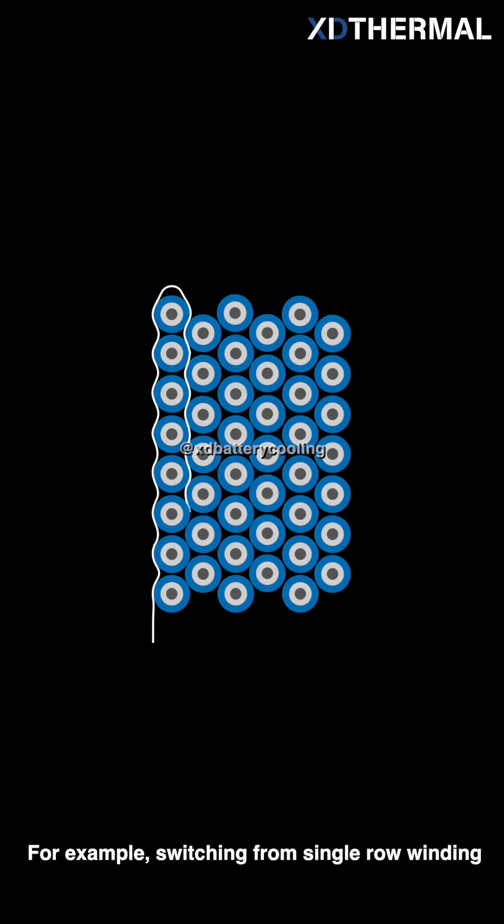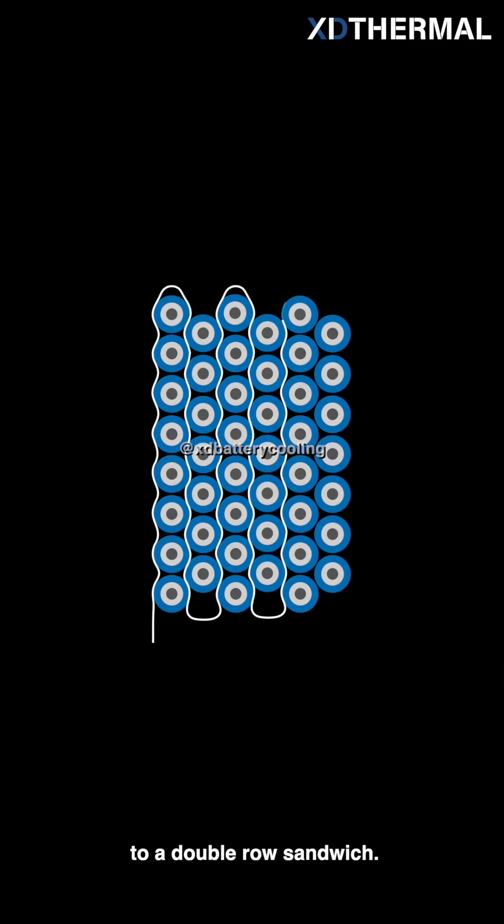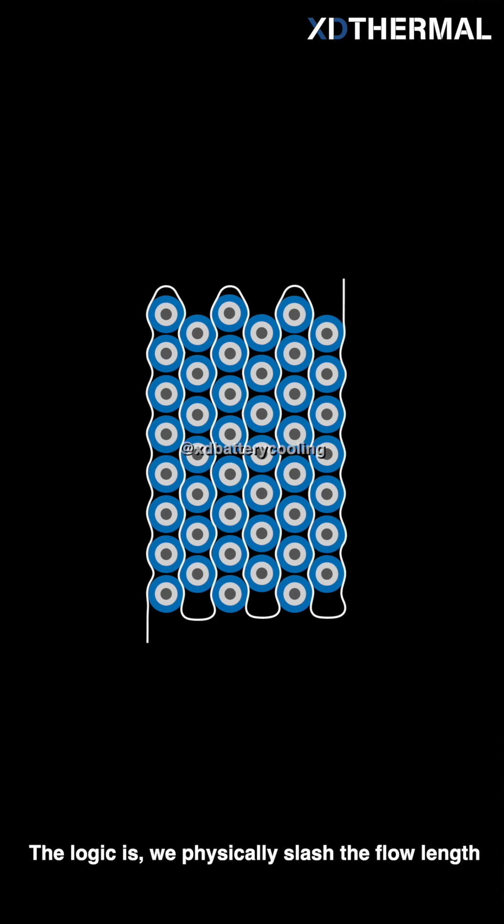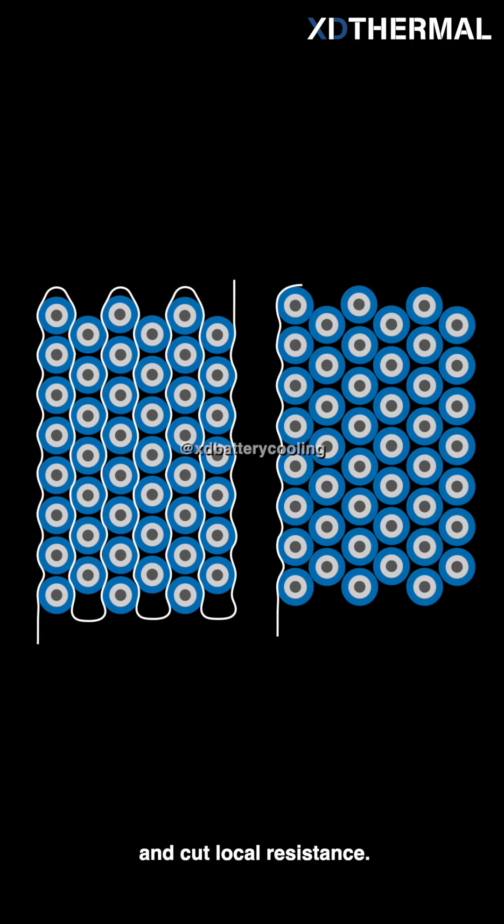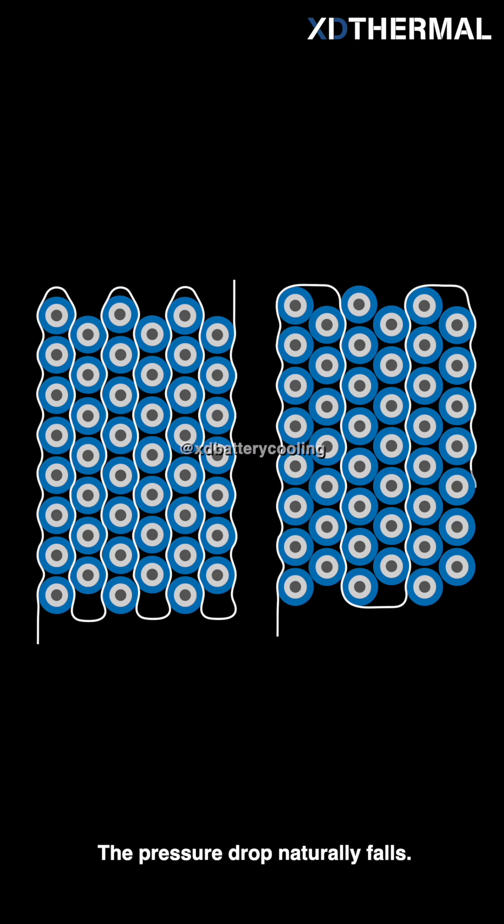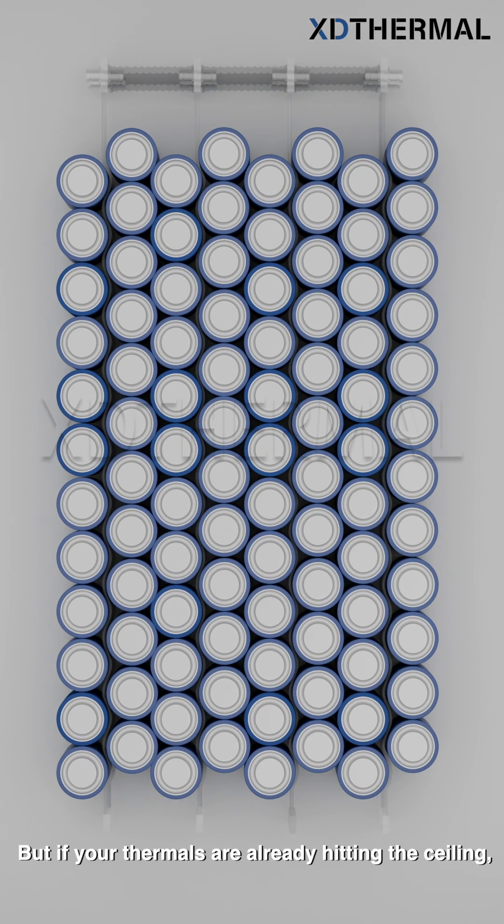For example, switching from single row winding to a double row sandwich. The logic is, we physically slash the flow length and cut local resistance. The pressure drop naturally falls.